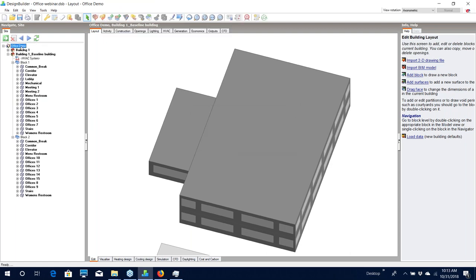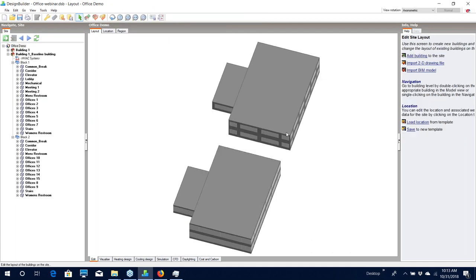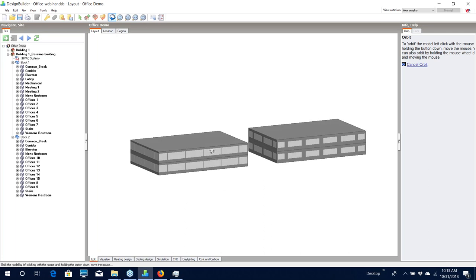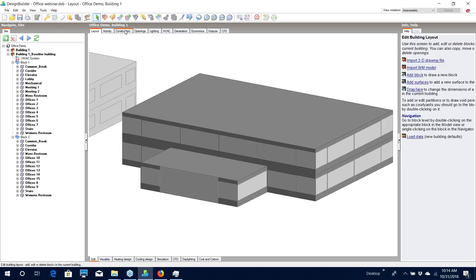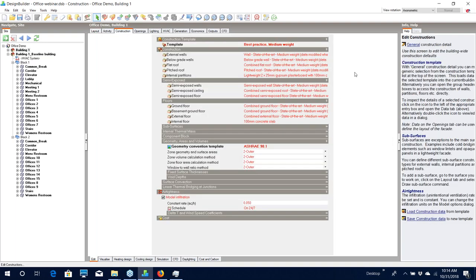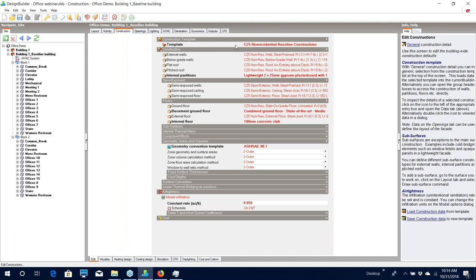The baseline building is now completed. If we look closely we can see clearly the difference between our proposed building with the 60% window-to-wall ratio and the baseline building with the 40%, including the change on our entrance facade. If we go to the Construction tab and look at the wall constructions, you can see that the constructions have changed to the appropriate ones for the climate zone selected for our building — Design Builder has automatically made these changes for us.